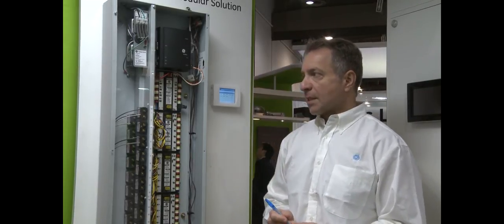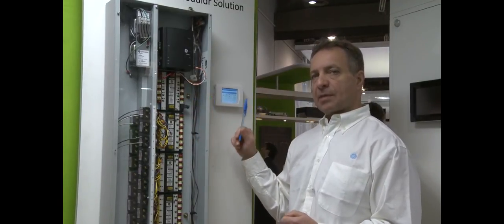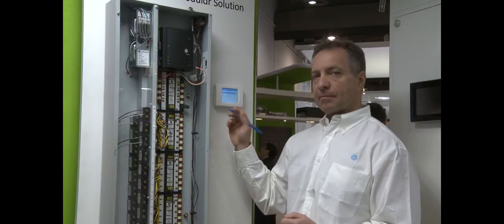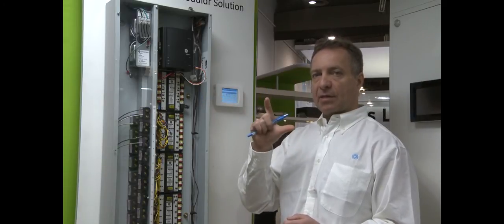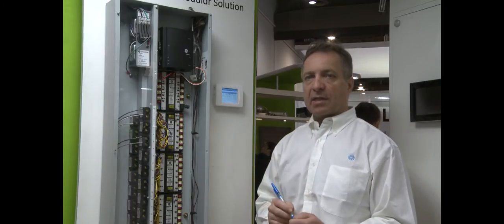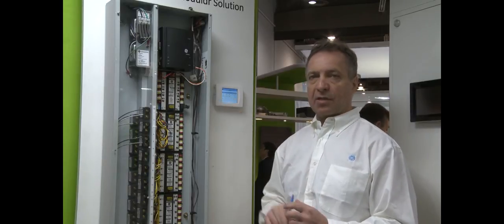For motion sensors, if we use occupancy sensors to any of these inputs, the system allows to set up time delay through the controllers instead of actually relying on the time delay on the sensor. The advantage is that if you want to change it, you don't have to climb the ladder and open the sensor. You can just come here and you can change your time delay.